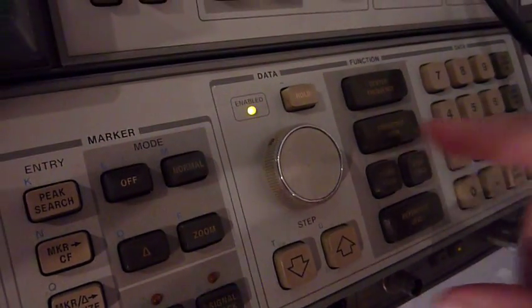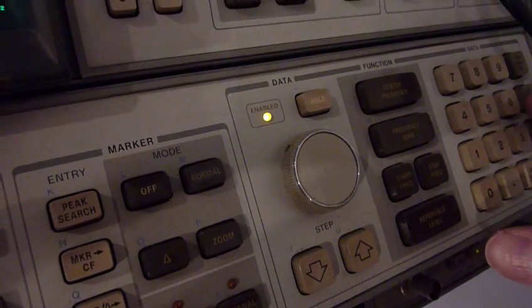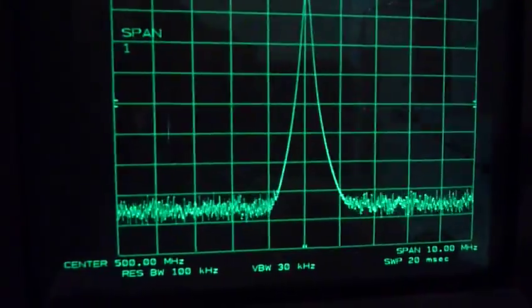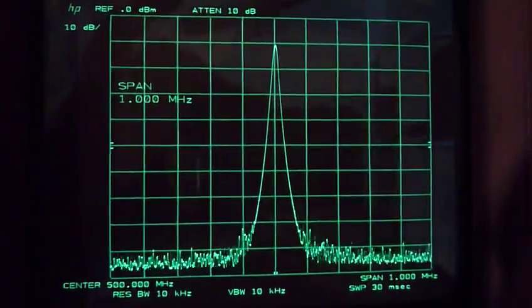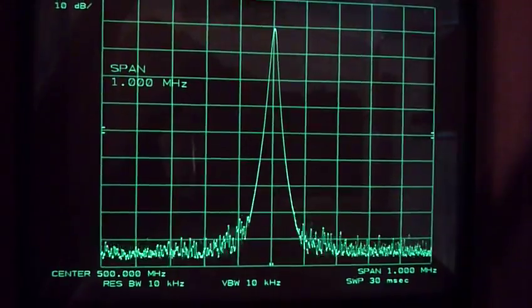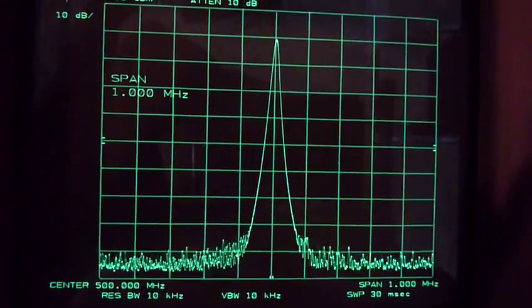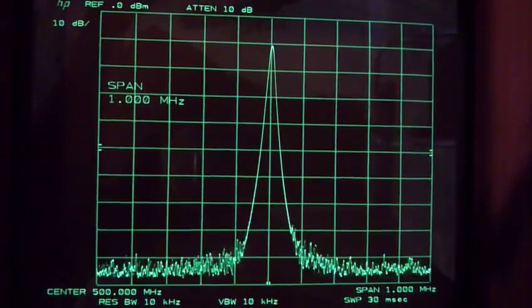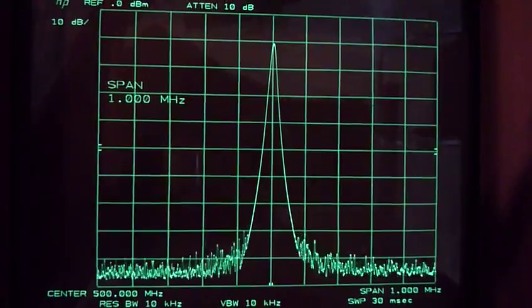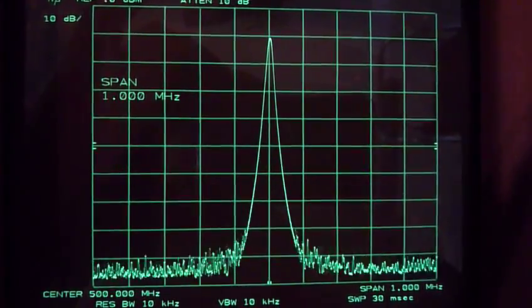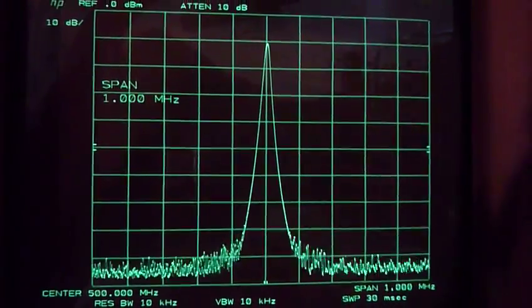And there's a third mode. That's when the frequency span is less than one megahertz. So let's do one megahertz. And sure enough, in that one, the YTO is not tuned. It's just locked at one specific frequency. And sure enough, this is beautiful. It works now. No more errors.